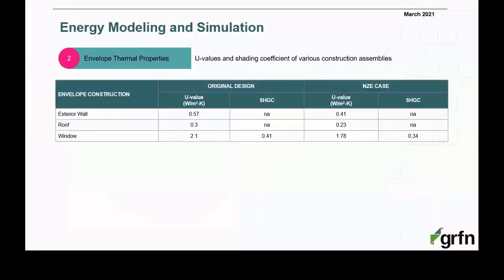On this slide, we can see the U values and shading coefficient of the original design versus the net zero energy building case. In the original design, it's basically the Dubai municipality requirements, whereas with the net zero energy case, we've improved on the U values. We didn't go for very drastic changes, so we need to keep in mind when we're designing buildings, we don't want to go above and beyond certain levels where the cost of the building will become too high. So we're trying to see what are the optimum U values to get the net zero and still not cost a lot of money.